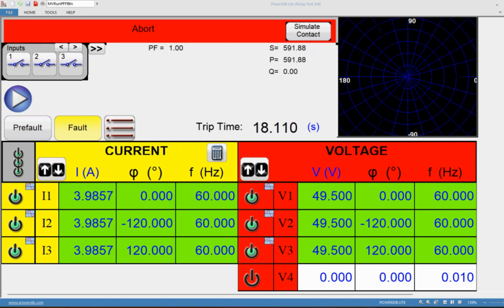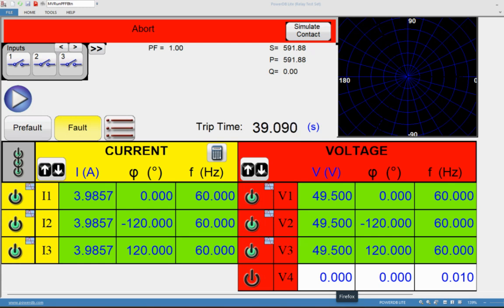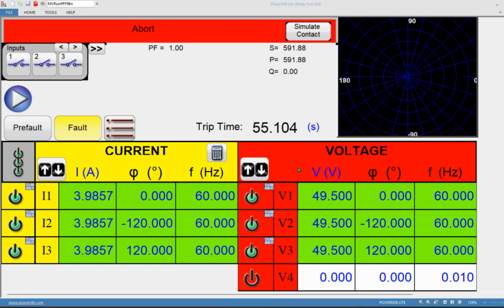When the user presses play, pre-fault and fault conditions with two different voltage sources are automatically injected. The tool superimposes two different waveforms — source one and source two — to create the power swing scenario. The relay sees the superimposed waveform, detects the impedance changes as a power swing, and blocks the impedance functionality. This is a simple way to test any relay in the market — ABB, Siemens, GE, Schneider — any impedance relay with a power swing feature using the fault calculator.